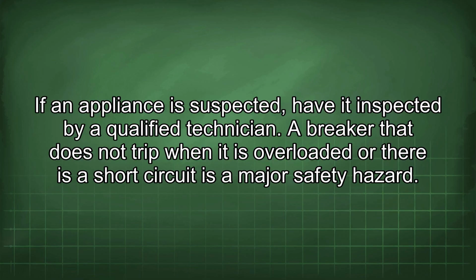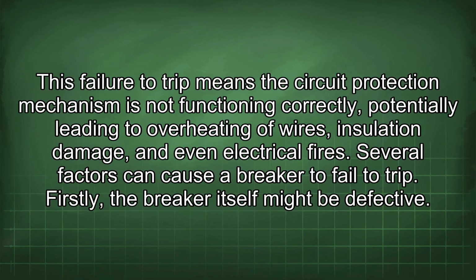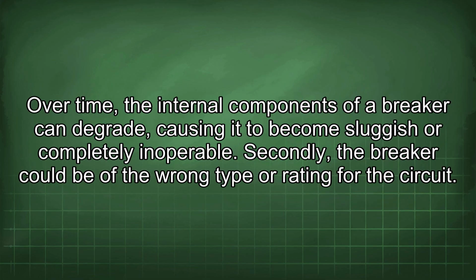A breaker that does not trip when it is overloaded or there is a short circuit is a major safety hazard. This failure to trip means the circuit protection mechanism is not functioning correctly, potentially leading to overheating of wires, insulation damage, and even electrical fires. Several factors can cause a breaker to fail to trip. Firstly, the breaker itself might be defective. Over time, the internal components of a breaker can degrade, causing it to become sluggish or completely inoperable.